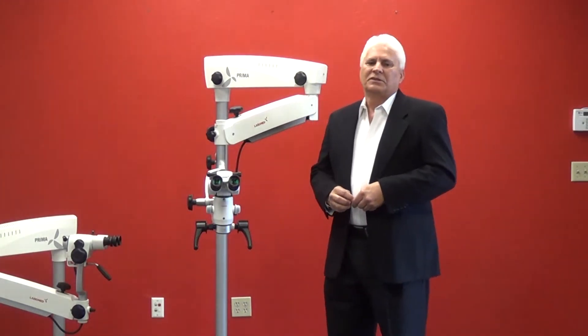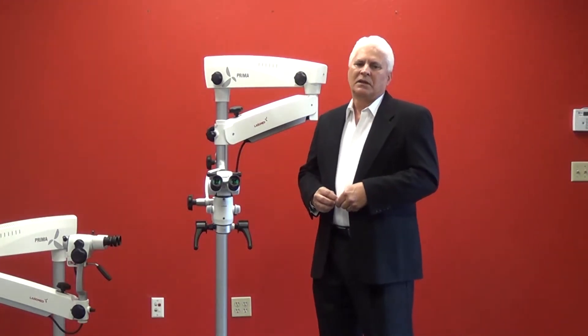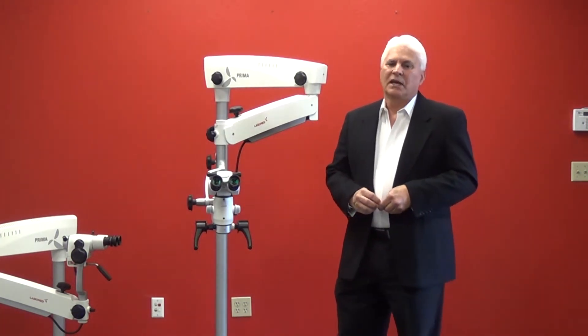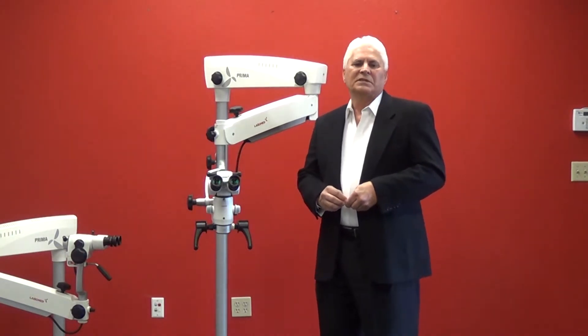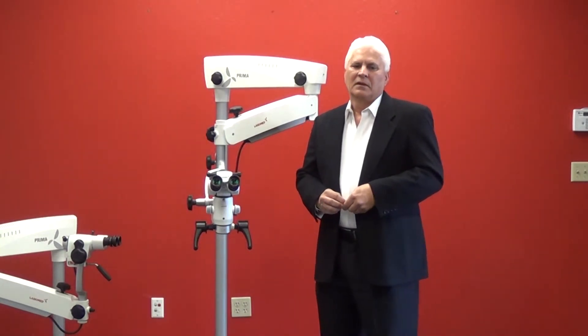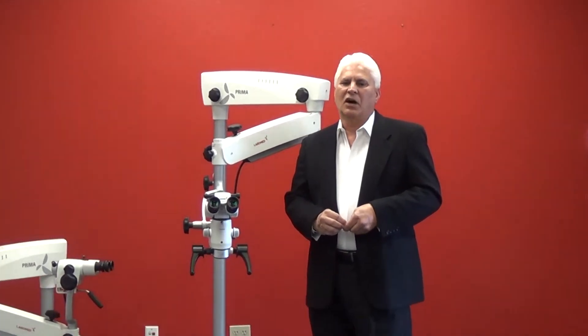The conventional technology, halogen, has a 500 hour lifespan, tends to have a yellow color temperature, and produces roughly 60,000 lux. Lux is a measure of light intensity. This results in an image with a biased color, as well as added cost with bulb replacements and more downtime.